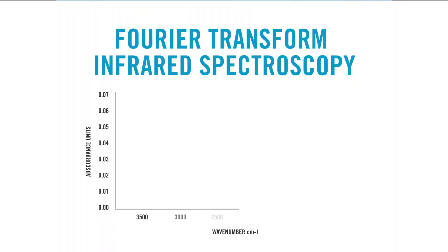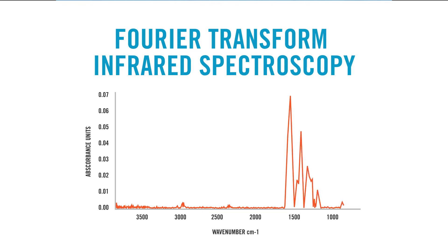Our next step is to look at the foulant using Fourier transform infrared spectroscopy. During this analysis, unique peaks are seen which correspond to different functional groups. This analysis revealed the presence of iron peaks, as well as calcium hydroxide peaks. No significant organic peaks were observed during this analysis, so we know that organics are not one of their main foulants.